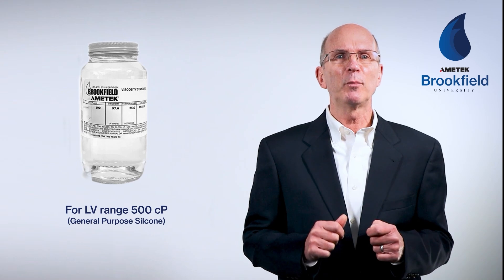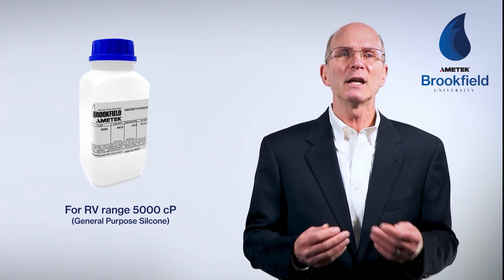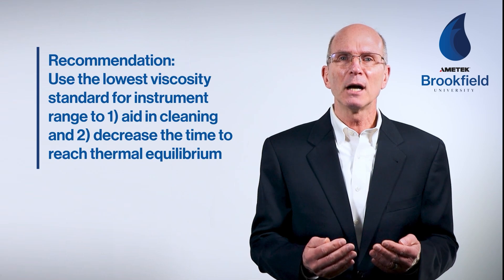Ametek Brookfield recommends using one fluid measured at three speeds, covering low, medium, and high torque to verify the linearity and accuracy of the spring over its full range. There is no need to use a standard in the same viscosity range as the material being tested. When using standard LV spindles, we recommend 500 centipoise general-purpose silicone; for RV range, 5,000 centipoise; for HA and HB range, 12,500 centipoise. We recommend using the lowest viscosity standard for your instrument range, which aids in cleaning and decreases the time to reach thermal equilibrium.